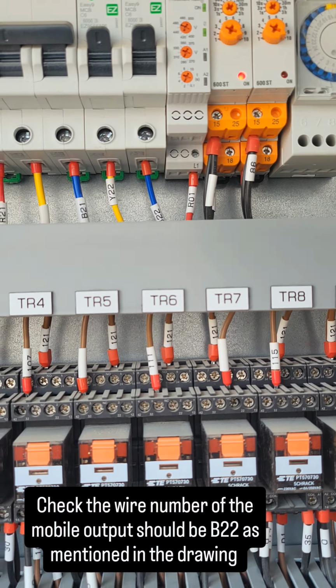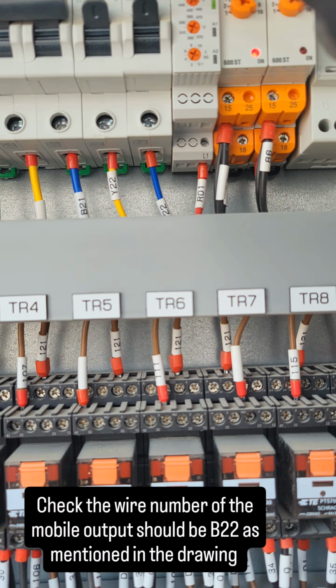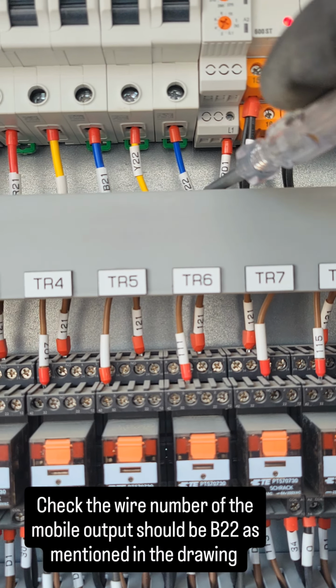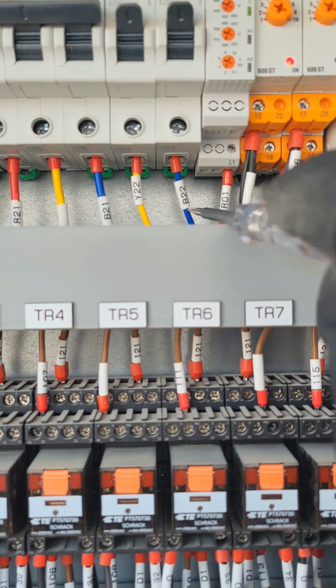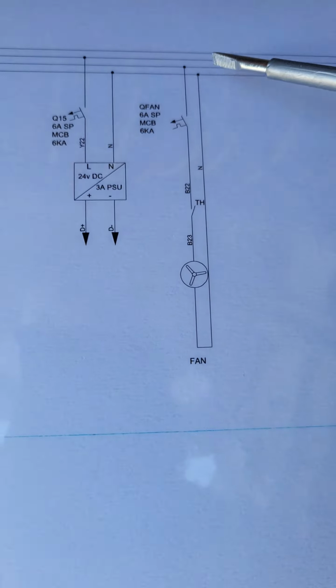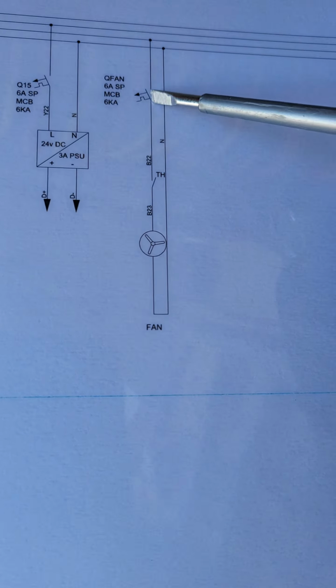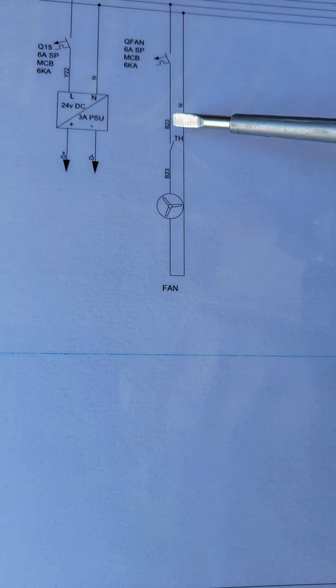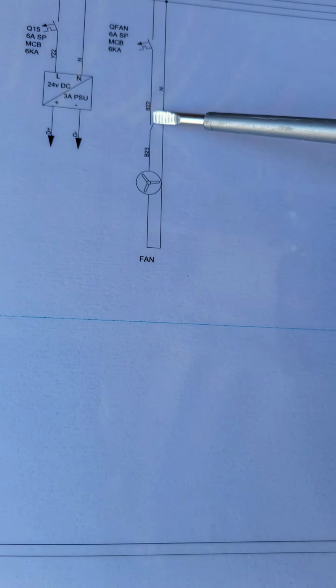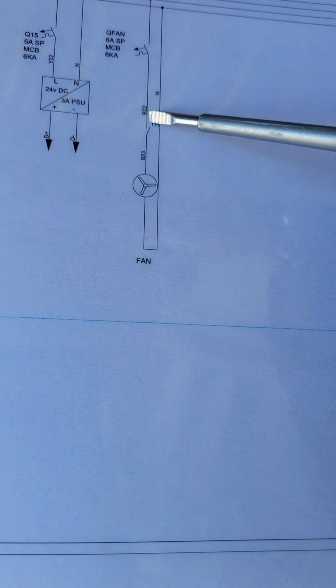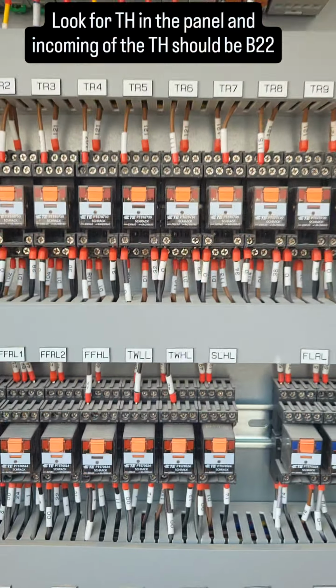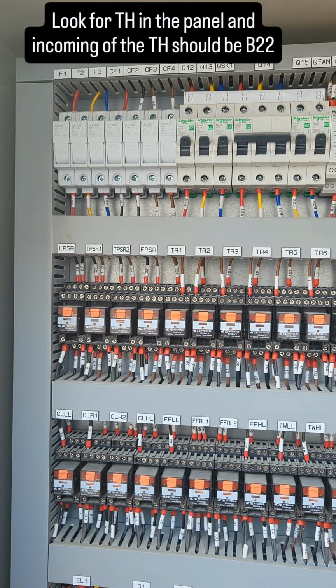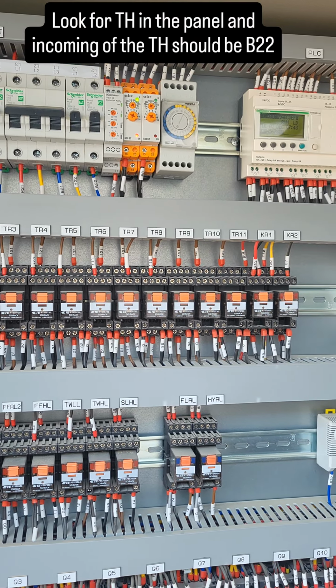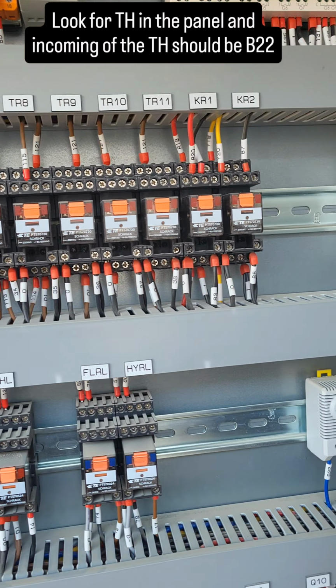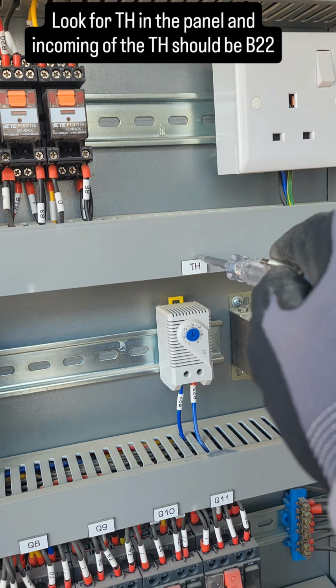And now we will check the wire number of the output of the MCB. It should be B22, and see, it is B22. Cross check the drawing, and the output of the MCB wire number is B22. So we are on the right path, and it goes to the TH. TH means thermostat. Now search for TH on the panel, and here you can see the TH on the right corner.